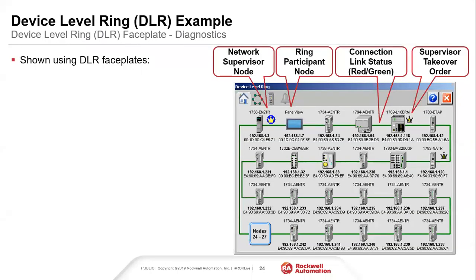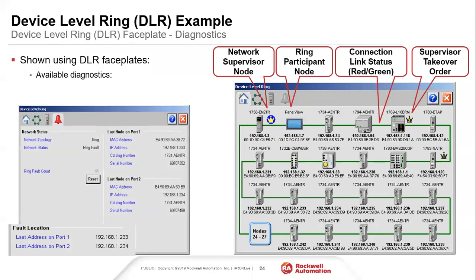Some of the benefits on this end, both from a panel view and also from our FactoryTalk View SE platform: the Studio 5000 environment for the ControlLogix and CompactLogix get diagnostics from this natively. There's a little add-on instruction that you can drop into your code. This is a faceplate that you add into the HMI. Everything that you see inside of it will automatically get populated. So it will build the DLR chain for you, granted, assuming you drop in that little AOI block.